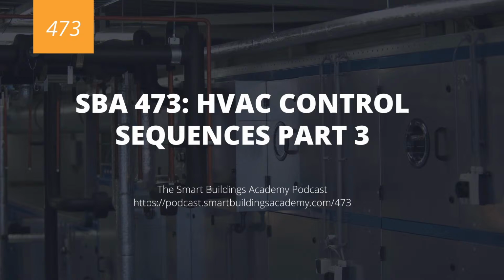When we're dealing with these type of units, we'll typically have cooling and we'll typically have reheat. Sometimes we will not see reheat at a mixed air single path variable air volume air handler because we will depend on the terminal units downstream to do reheat at the space and zone level.